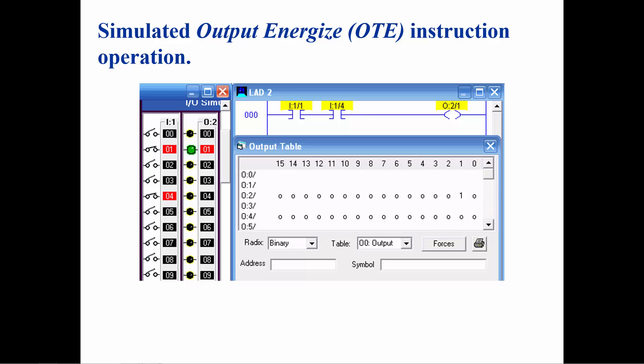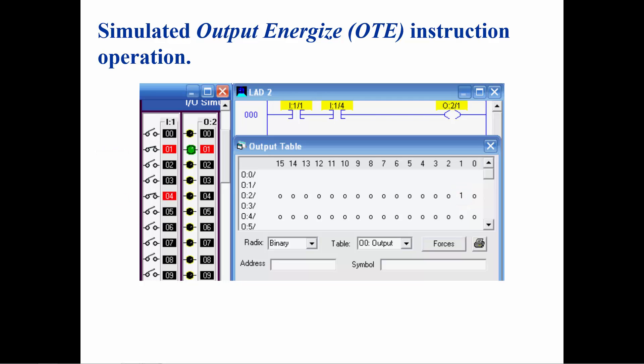When the two examine if closed instructions are true, there will be logic continuity on this rung to the output energized instruction. When the instructions before the output energized instruction are true, a 1 will be placed in the output table at O colon 2 slash 1, and the physical output with that address will be turned on. If the rung is false, a 0 will be placed in the output table and the physical output with that address will be turned off.